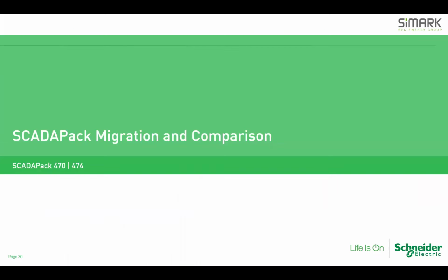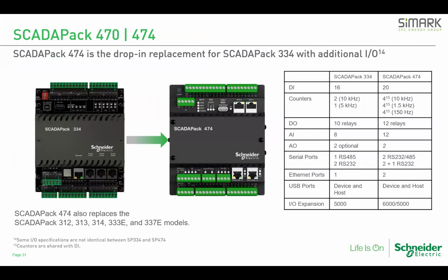Let's have a look at the existing SCADAPacks and where the new 470 and the 474 might fit in from an I/O comparison. So the existing 334 RTU maps very nicely into the new 474. You can see here on the right, there's some of the differences. We're supporting more digital inputs, more digital outputs, more analogs, and as opposed to the 334 having optional analog outputs, we now provide 2 analog outputs right out of the box.